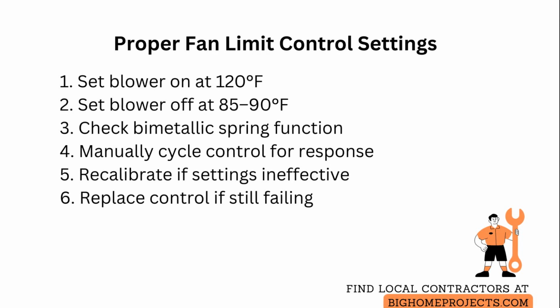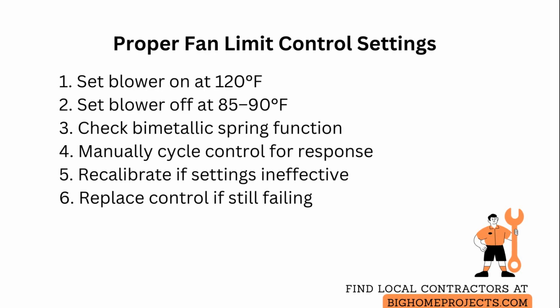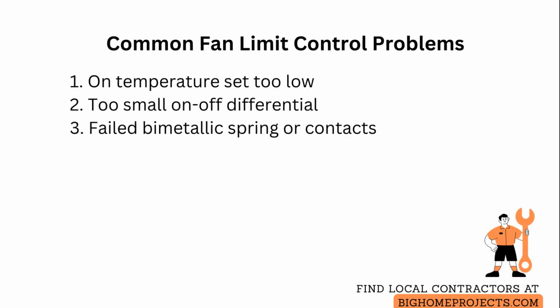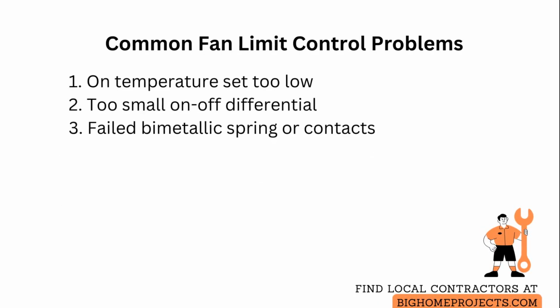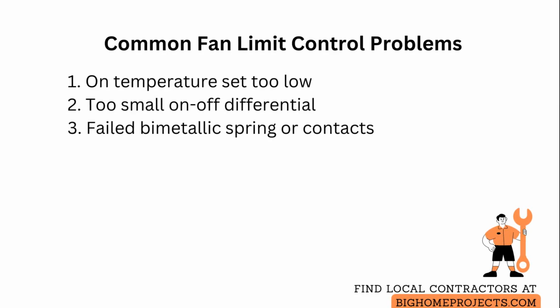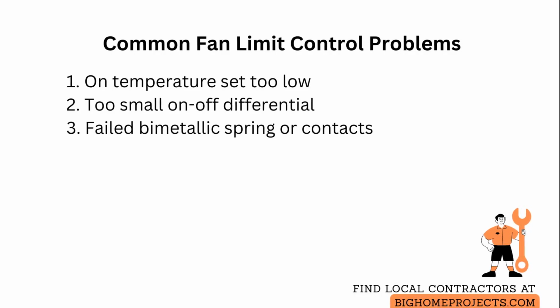Keep a temperature probe handy to spot check the actual plenum temperature versus the control settings during a normal heating cycle. Common mistakes include setting the on temperature too low, which makes the blower run too early and wastes energy. So raise the on point to 120 degrees and verify the blower starts only after the exchanger reaches that temperature.